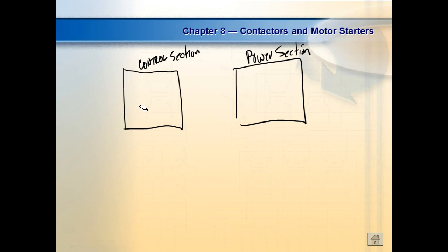So contactors, the main contacts on contactors go over here. Now it might have some auxiliary contacts over here, but these are going to be little old tiny contacts, right? I passed that relay around to you how many times now? Two or three, with the little auxiliary contacts on the side, big power contacts on the top. Then I showed y'all this one, where the auxiliary contacts are on the top and the power contacts are on the bottom. The one that we're going to use is this guy right here.